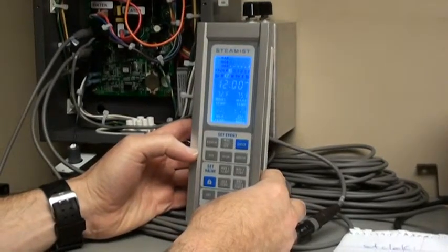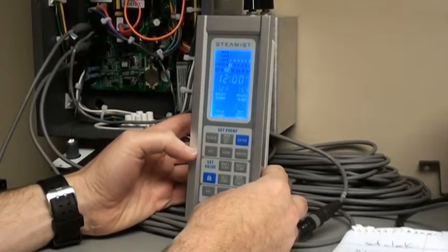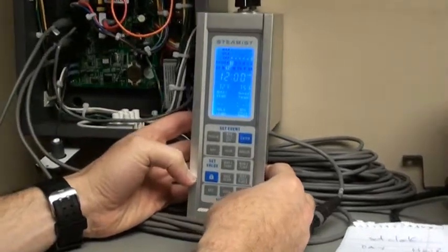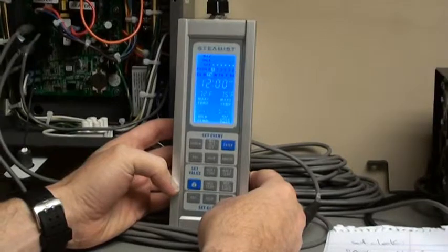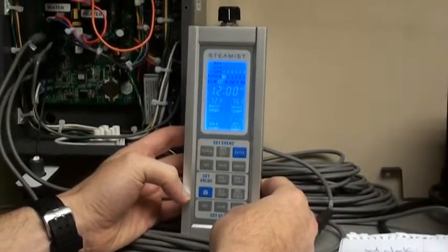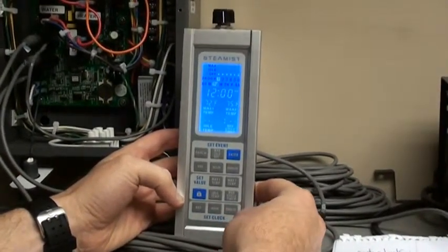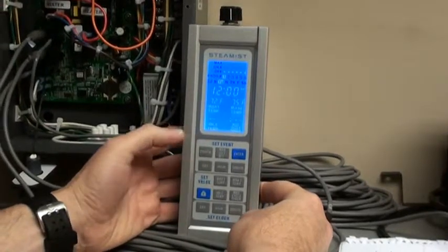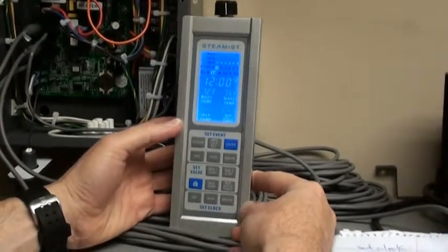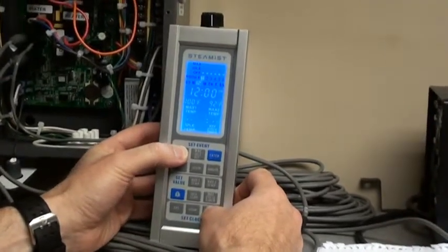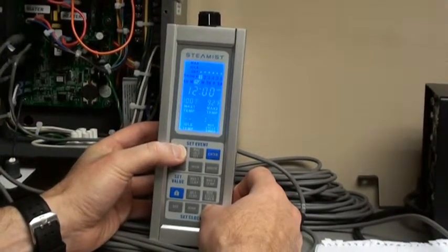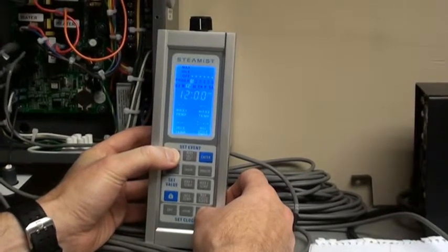We will start programming a commercial digital control package with serial numbers 40,000 and above. First step we'll do is reset the entire system. To reset it, we will push and hold the upper left program button and bottom right minute button. We will hold them for approximately 5 seconds. We'll know it's reset when max 1 and max 2 temps go to dash dash, such as now.